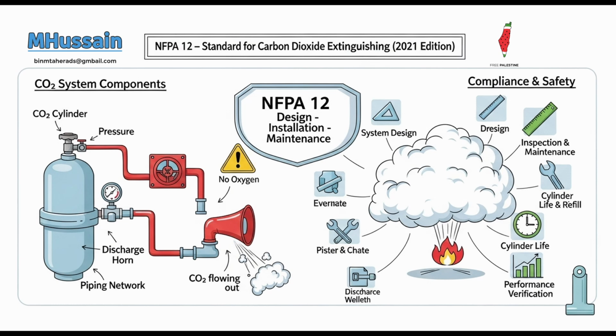Reactive metals. Okay, why not? The reason is fundamental. These materials either don't rely on atmospheric oxygen for combustion, or they react in ways that CO2 simply cannot suppress. So it just doesn't work on them. It doesn't. However, there's a crucial nuance. While CO2 doesn't extinguish these specific fires, the standard notes it does not react dangerously with these materials or increase their burning rate. Oh, that's interesting. It doesn't make it worse.